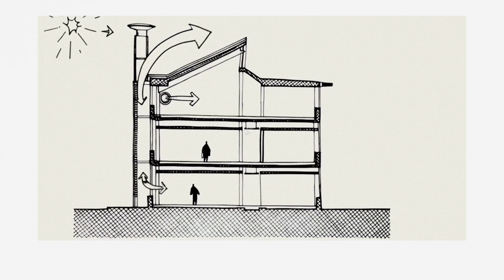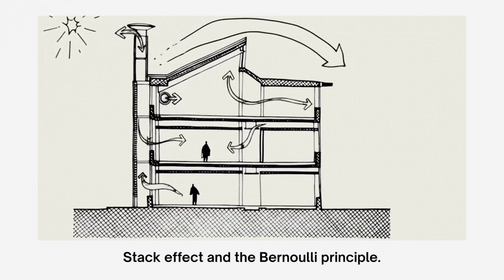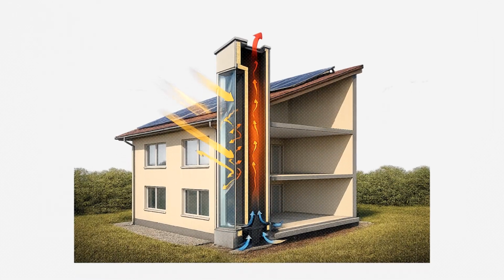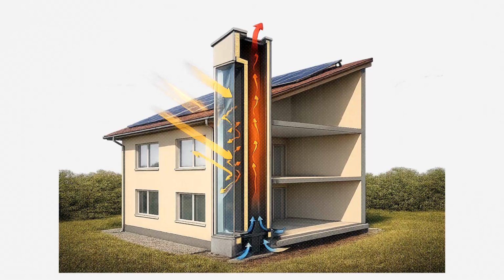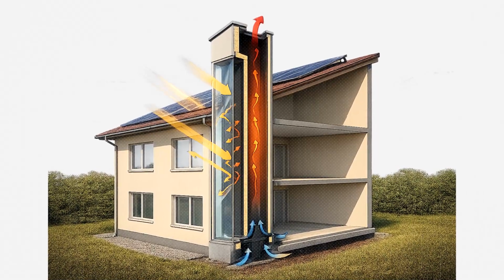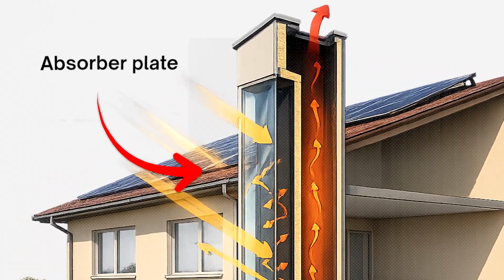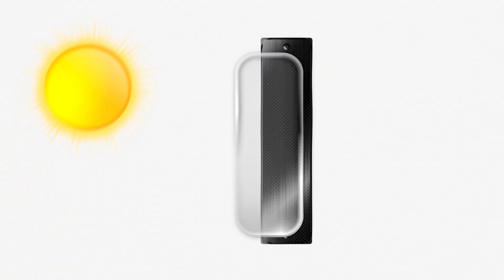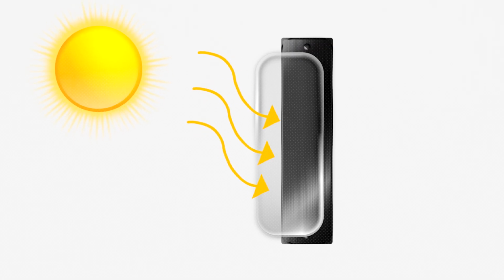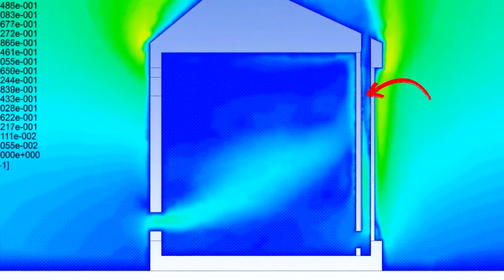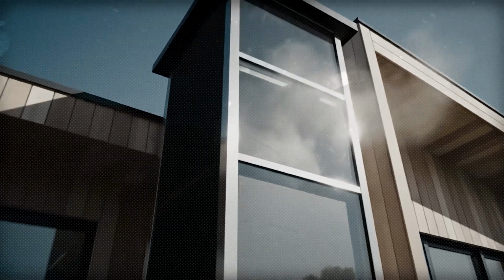It comes down to the stack effect and the Bernoulli principle. Here's what happens inside the system. A solar chimney is essentially a vertical shaft engineered to capture as much solar energy as possible. At its heart is an absorber plate, typically a dark-coated metal or masonry surface, set behind a layer of high-transmittance glass. Sunlight passes through the glazing, strikes the absorber, and gets converted into radiant heat. Per the ideal gas law, that heat lowers the density of the air inside the shaft. Lighter, energized air rises and exits through the exhaust at the top.